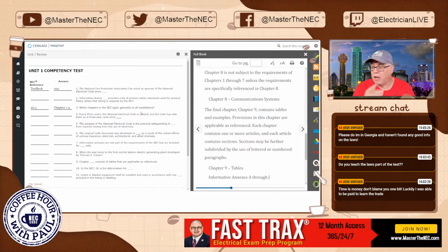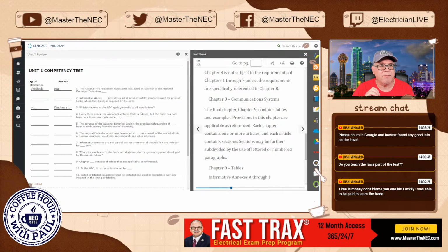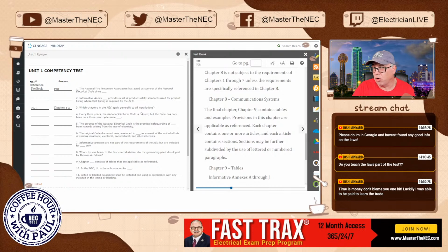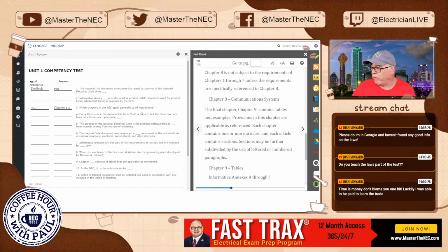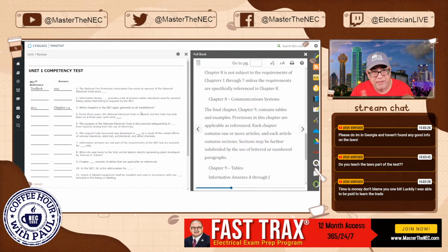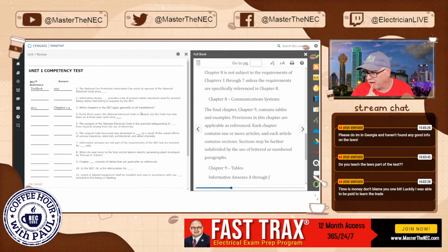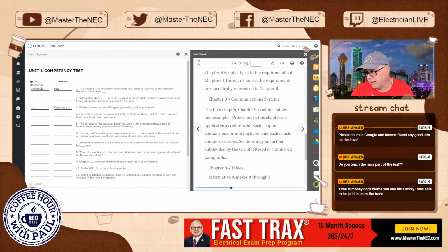For example, another TikTok video I did, I explained something about MC cable in the steel versus the aluminum, and you couldn't use a set screw. The reason I say it that way is, one, because I work with the manufacturer that makes MC cable, and we do not want people to use our set screw type of fittings on our aluminum MC.